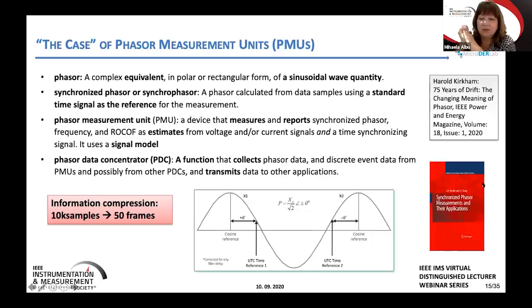Now, I would not repeat what a phasor measurement unit is, because we know it measures and reports synchronized phasors and other quantities. These quantities are of high interest because we use frequency without having it measured with the highest resolution and accuracy today in normal operation of power systems - about 1 microhertz - and the rate of change of frequency. Without these quantities, we might not see deployment of PMUs as large as we see today.